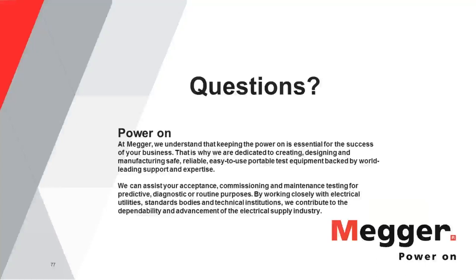So there's a point where insulation testers would not be able to help you on these activities, and they might be good for when you have a very bad situation on a cable and you need to determine if it's a go, no go, but not for diagnostics or cable fault location. For that, definitely you need something else, and we are talking about medium voltage and up.